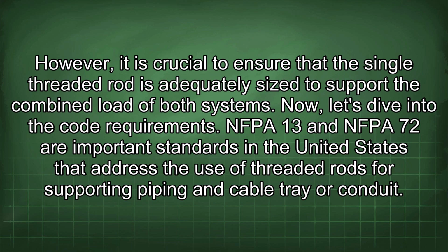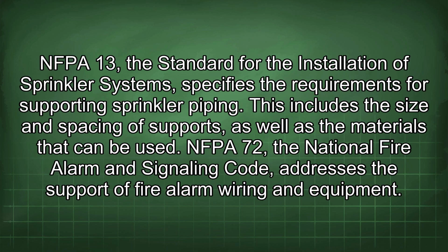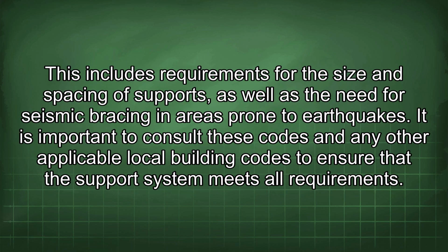NFPA 13 and NFPA 72 are important standards in the United States that address the use of threaded rods for supporting piping and cable tray or conduit. NFPA 13, the standard for the installation of sprinkler systems, specifies the requirements for supporting sprinkler piping. This includes the size and spacing of supports, as well as the materials that can be used. NFPA 72, the National Fire Alarm and Signaling Code, addresses the support of fire alarm wiring and equipment. This includes requirements for the size and spacing of supports, as well as the need for seismic bracing in areas prone to earthquakes. It is important to consult these codes and any other applicable local building codes to ensure that the support system meets all requirements.